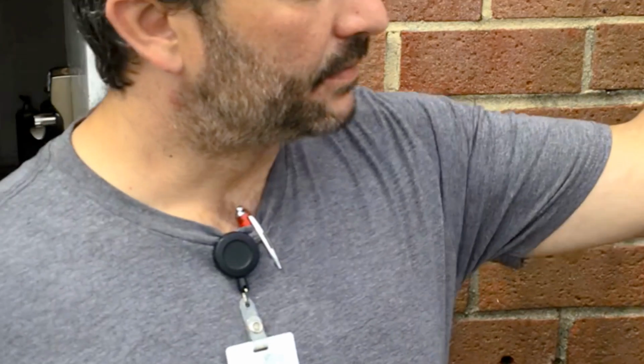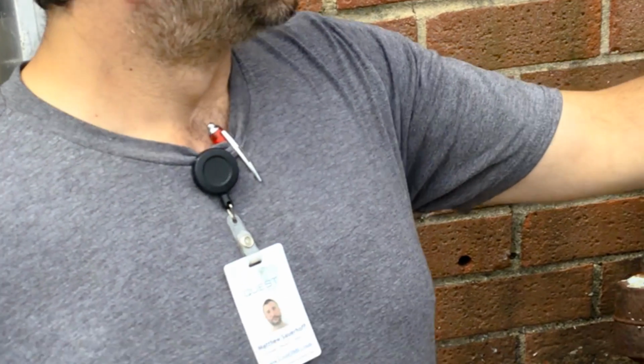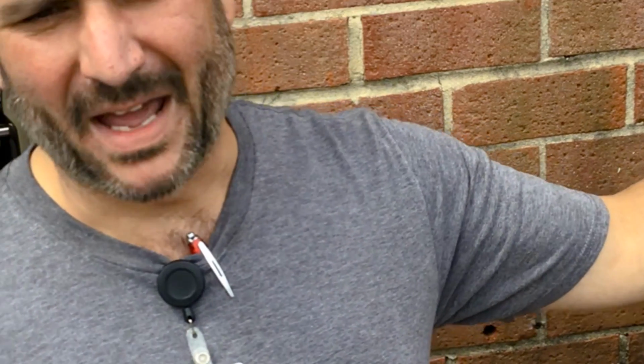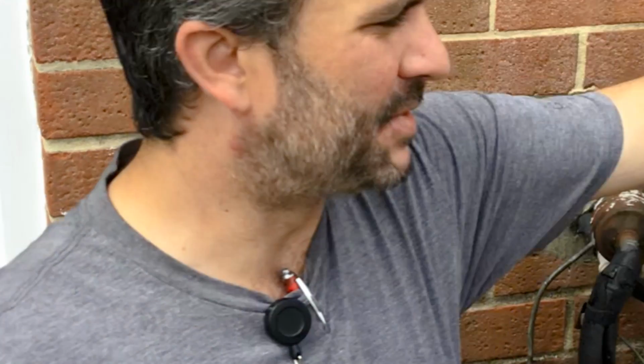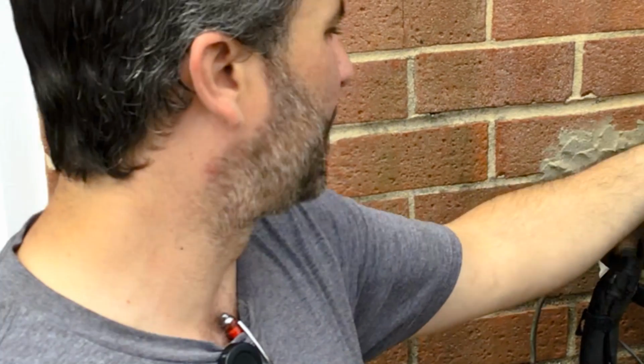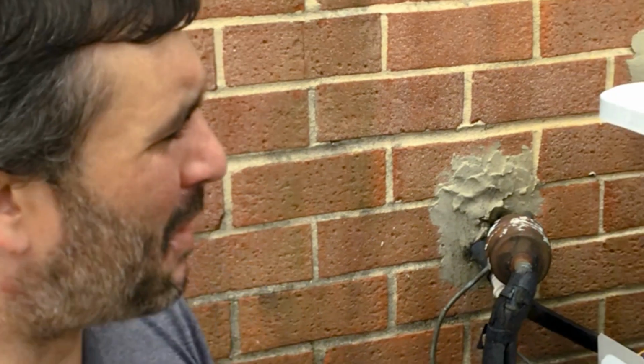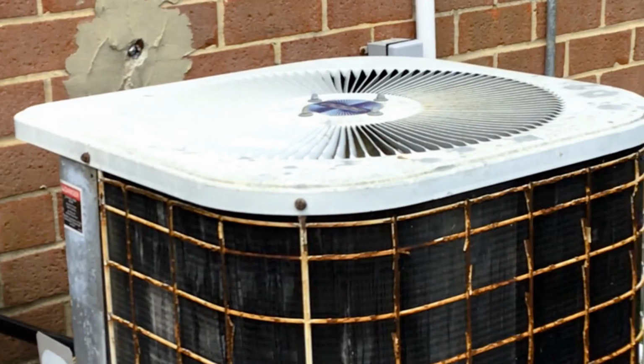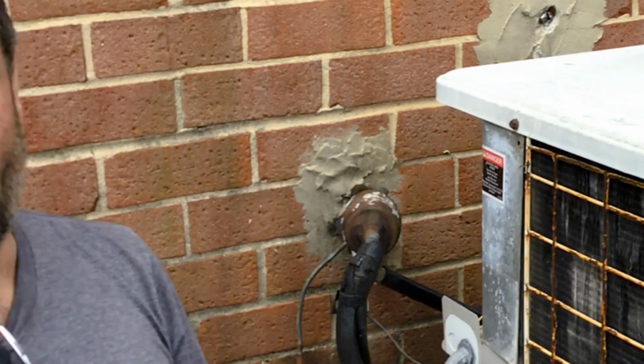So with those few easy inspections, you can tell if you have a bad motor or not. Changing out a fan motor is pretty simple. You just have to run your wires through the casing. There are 4 bolts on top. The most difficult part is getting the blade off of the motor shaft.